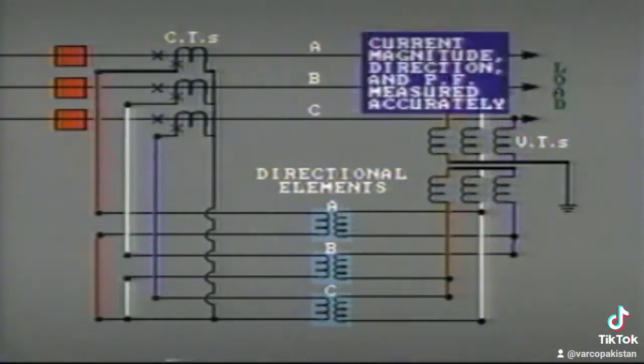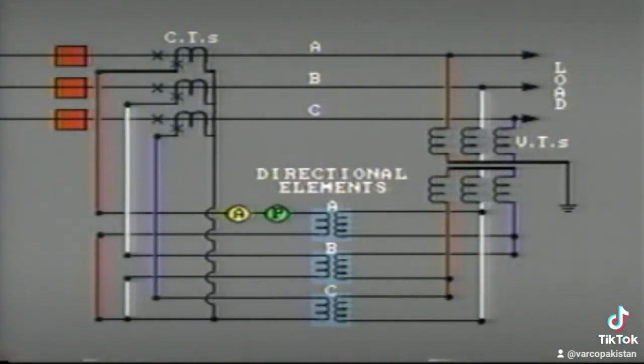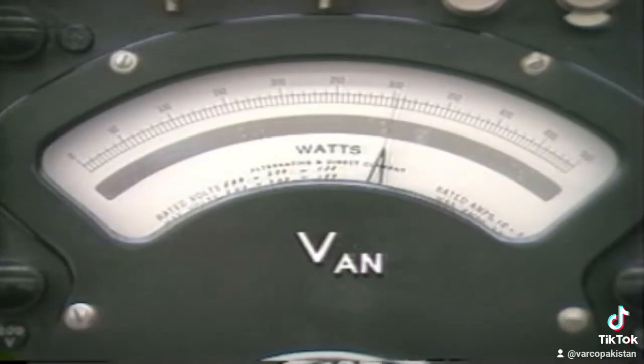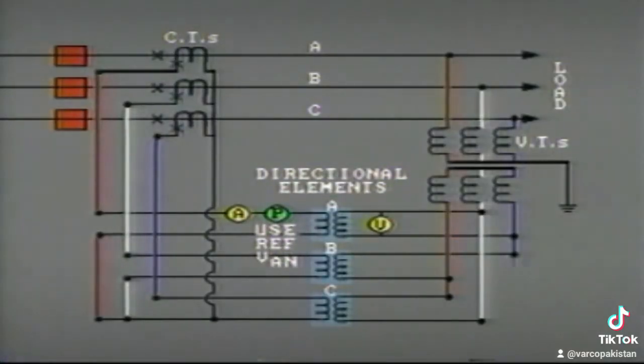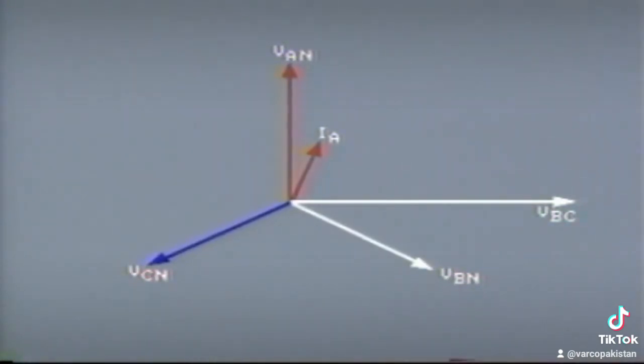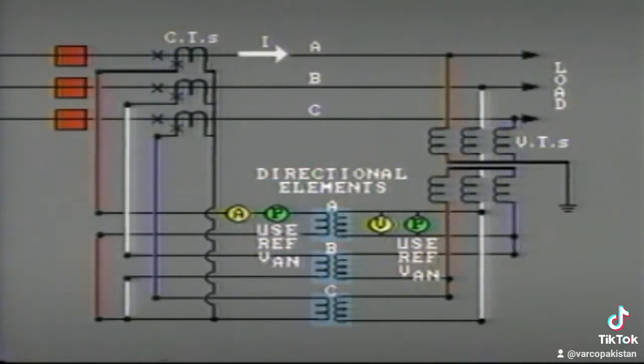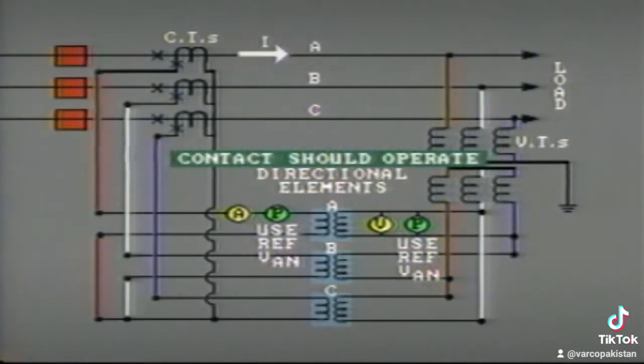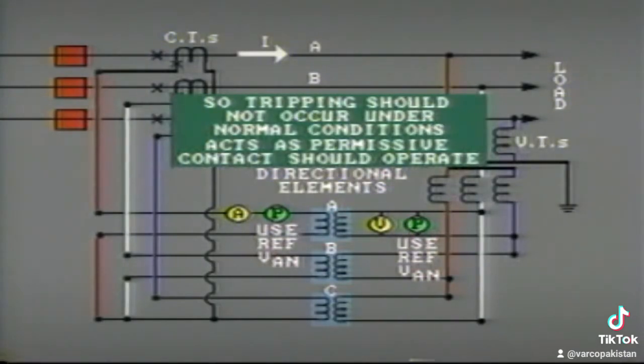To check the phase relay, the load current magnitude, direction, and power factor must be measured accurately. Also, the value of current and its phase angle provided to the phase A directional relay. The phase angle meter should use as a reference voltage the A phase to neutral VAN. If a phase angle meter is not available, a watt meter could be used with its voltage coil connected phase A to neutral. We must also accurately measure the voltage input to the relay and its phase angle relative to VAN. This will enable us to draw a phasor diagram indicating the relative phase displacements of current, IA, and the polarizing voltage. With current flowing in the designated tripping direction, usually into the line, the directional element contact should operate. This will act as a permissive to the overcurrent or other protective element. So tripping should not occur under normal operating conditions.